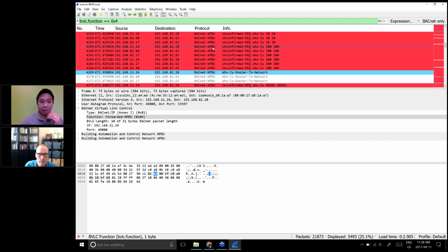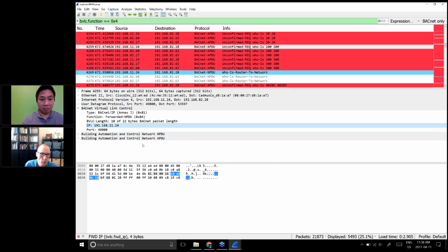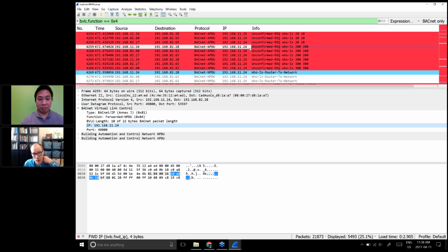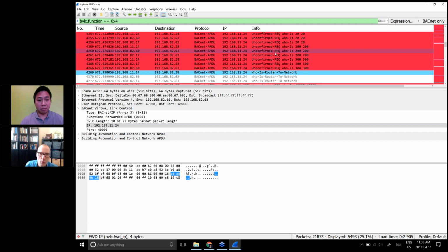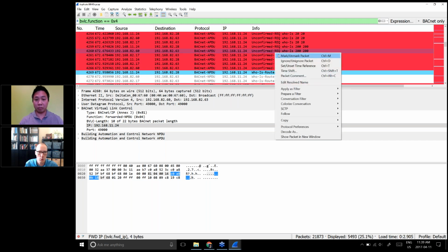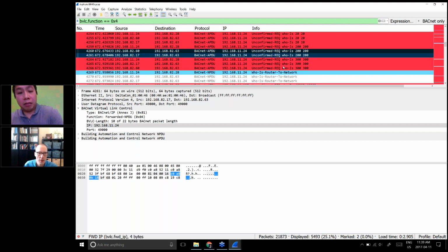Now notice how, yeah, like that Who-Is 200. You see how there is a Who-Is 200 and it's repeated 3 times in our capture? If we look over at the source IP, we'll see that it started from 11.24, and that's true. That's actually where it came from. But then notice that the next 2 lines send it out again as 82.60 and 82.17, both sent to the same destination, which is a subnet broadcast. So I'm looking at packets 4260 and 4261 here in this capture as confirming that there are duplicate BBMDs, because there's no rationale for that packet as a forwarded NPDU to be repeated by more than one IP source in my own network. It really only would come from one IP if there was one BBMD. So it's those 2 guys there, exactly, yeah.